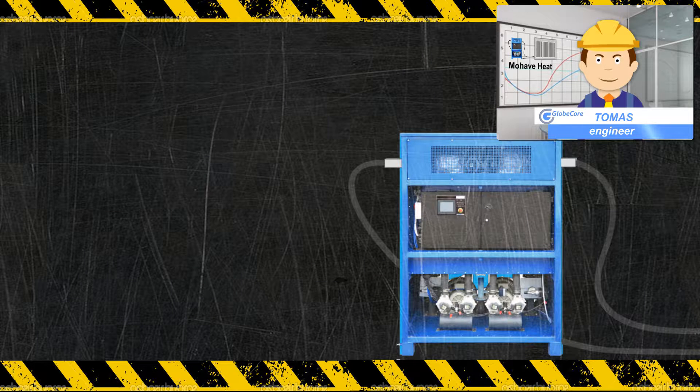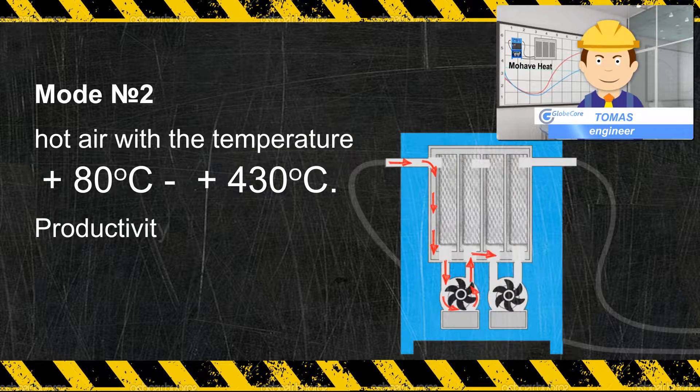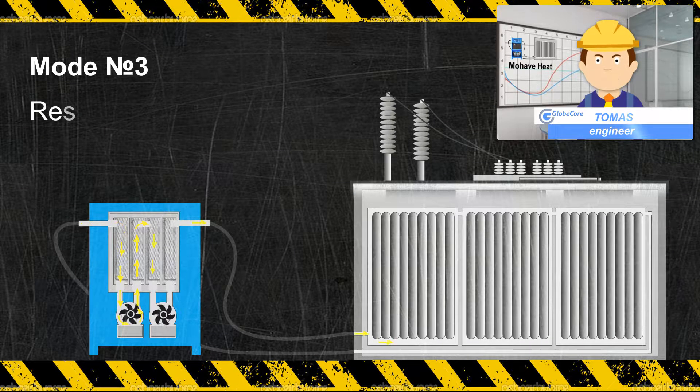This equipment provides hot air with a temperature from 80 to 400 degrees Celsius at up to 200 cubic meters per hour, which can be used to dry sorbents such as silica gel and zeolite. Temperature regulators and frequency converters provide the lowest possible power consumption.